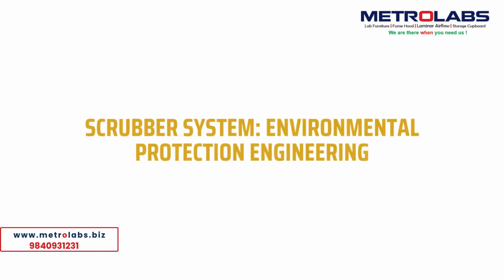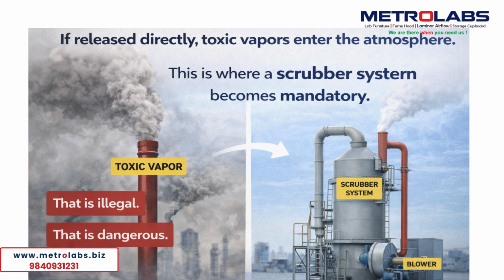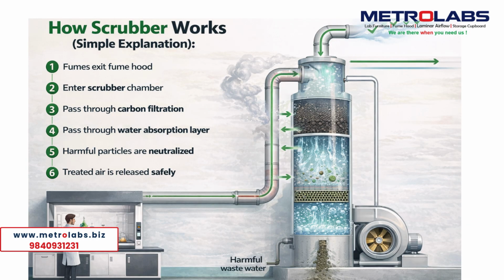Scrubber system, environmental protection engineering. Now let us talk about something most suppliers ignore. What happens to the fumes after they leave the fumehood? If released directly, toxic vapors enter the atmosphere. That is illegal. That is dangerous. This is where a scrubber system becomes mandatory. How a scrubber works, simple explanation. 1. Fumes exit the fumehood. 2. Enter the scrubber chamber. 3. Pass through carbon filtration. 4. Pass through a water absorption layer. 5. Harmful particles are neutralized. 6. Treated air is released safely.